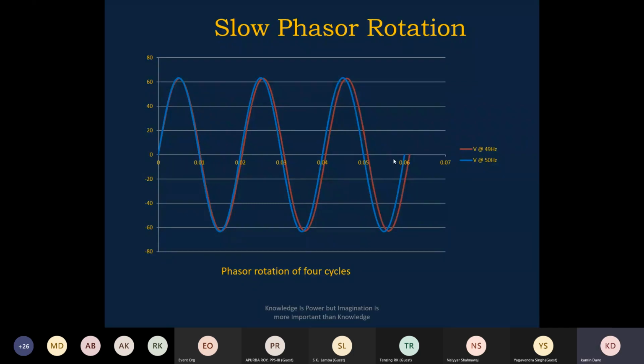Normally, we represent the frequency as 50 cycles per second. So it is 49 cycles per second, let us say. So in one window, you will see faster rotations, slower rotations, faster rotations, slower rotations, if the slip frequency difference is 1 hertz. This is how the frequency difference looks for the 3 cycle window.